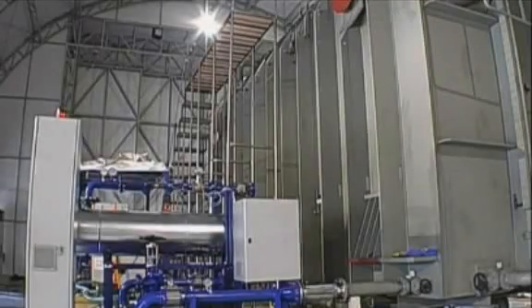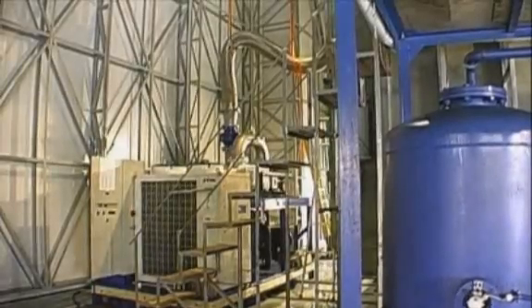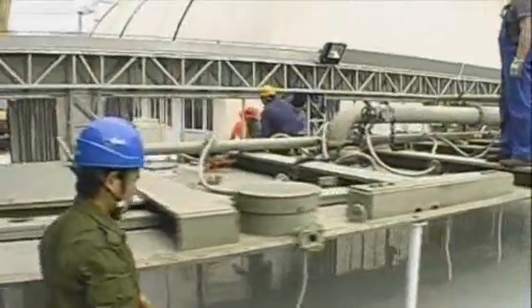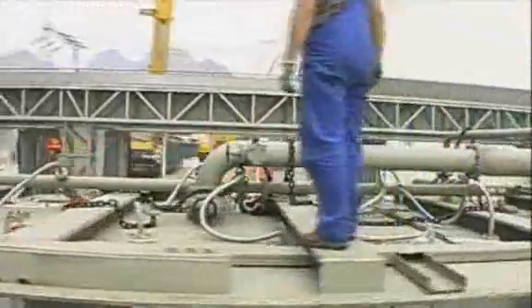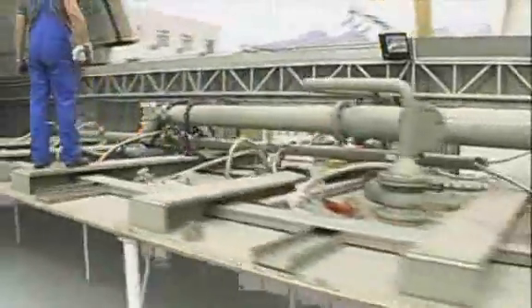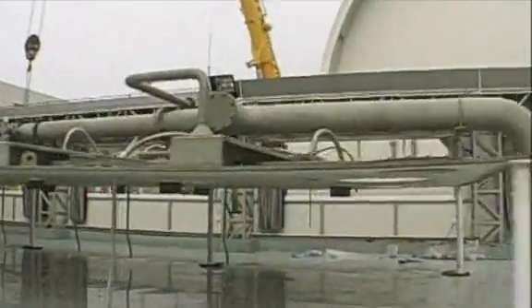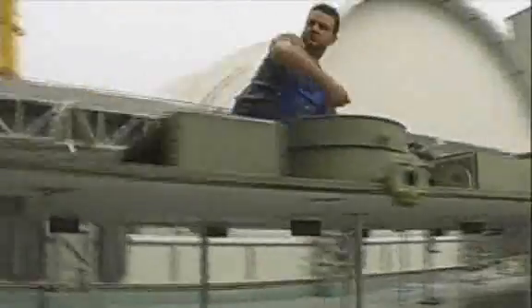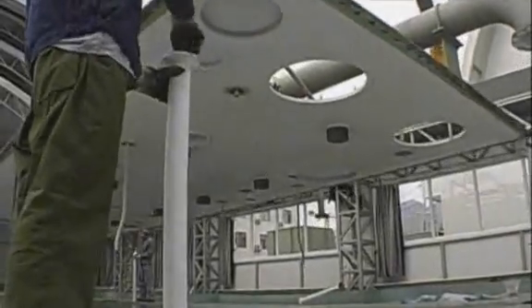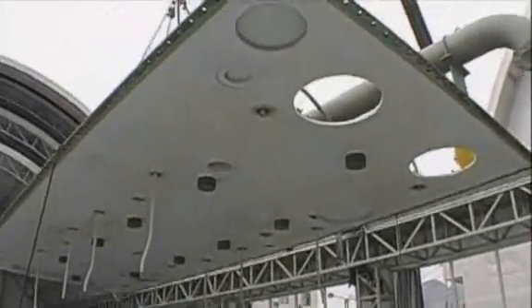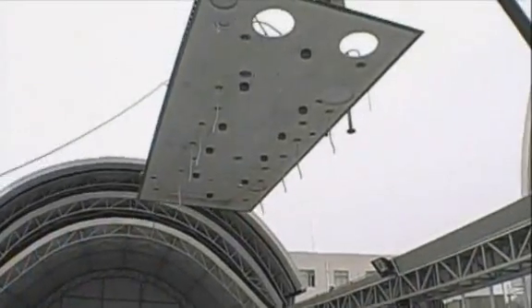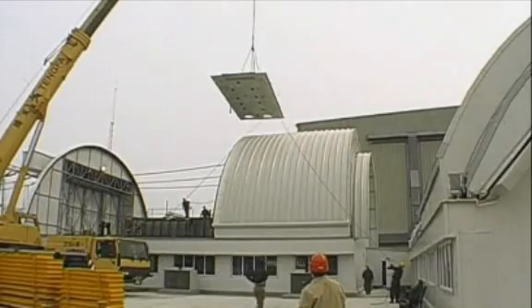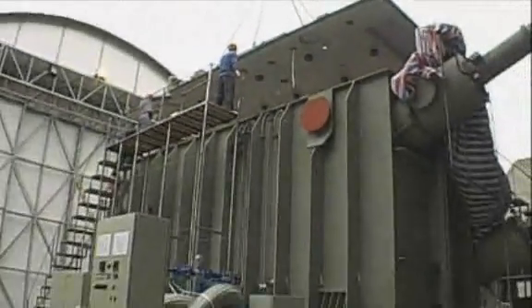Another special process: drying of the active part utilizing the oil spray method. Because no furnace is available locally, oil spraying takes the place of conventional factory active part treatment. The tank cover has to be modified to allow oil to be sprayed into the transformer at a high temperature. The lines and nozzles are designed so that they can be easily removed after the drying process is finished.